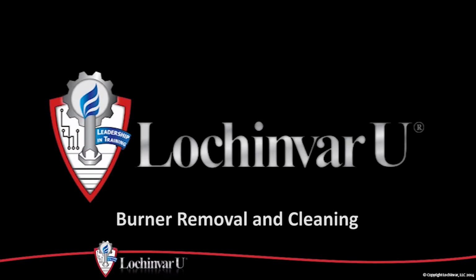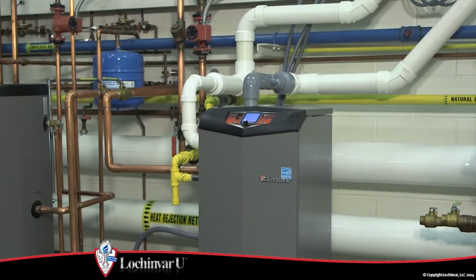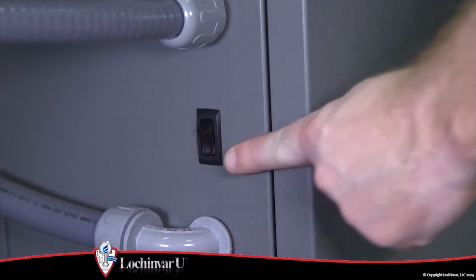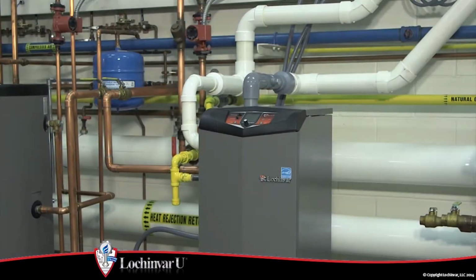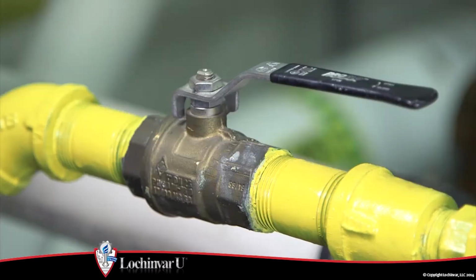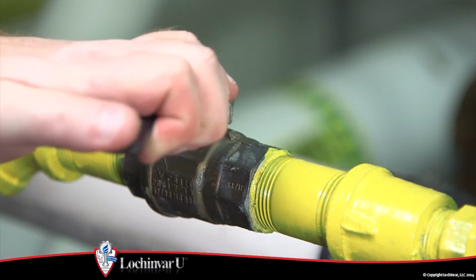Burner removal and cleaning. Locate the on-off switch on the side of the unit. Turn the switch to the off position. Turn off the main gas supply to the unit at the external main manual gas valve.